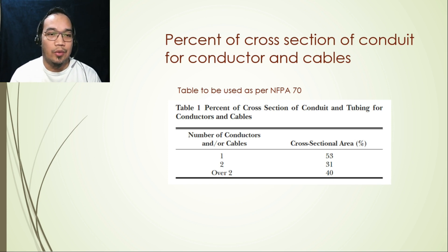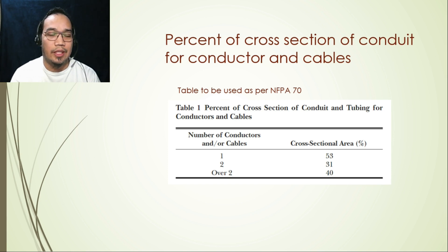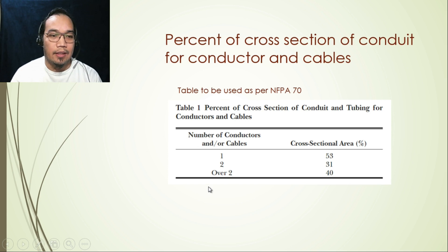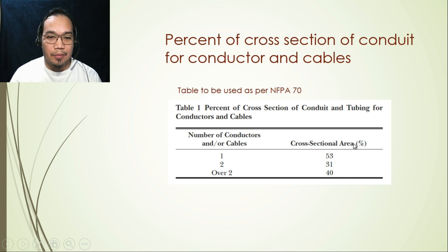Now that we know the types of cables and conduits used in fire alarm installation, we can look at the requirements of NFPA 70 for the quantity of cables permitted inside a conduit. There is a table in NFPA 70 that states: if you have one conductor or cable, the permitted cross-sectional area fill is only 53 percent — meaning only 53% of the conduit's cross-sectional area can be filled.